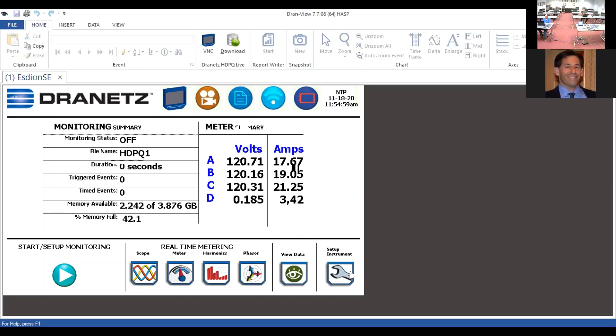Let's look at the first scenario, which is archiving the data to a thumb drive. Once you insert the thumb drive into the USB port on the instrument - and Ross mentioned this earlier - you want to make sure the instrument has acknowledged that it sees the thumb drive. It does that by giving you the thumb drive symbol in the icon that looks like a computer screen. Once we have that acknowledgement, we're ready to go to the next step, which is navigating to the appropriate screen that will allow us to download the data.